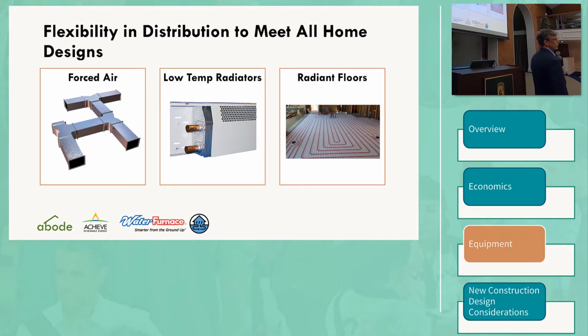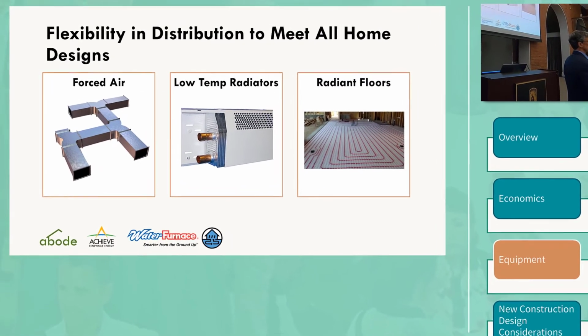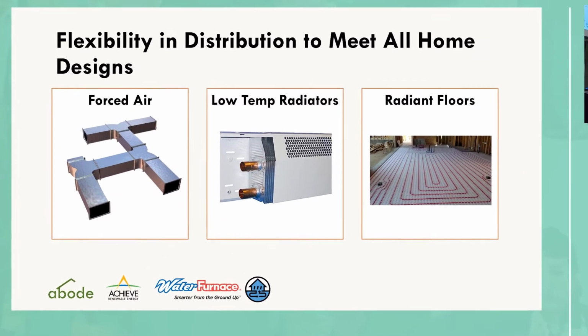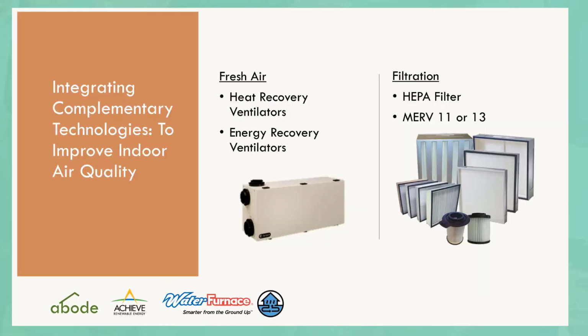can make things warm or cold. And without ducting, you don't get the air conditioning, unless you do something fancy like a chilled beam, but you're not going to do that in a house. Pairing with radiant floors is exceptionally efficient because the fluid temperatures are lower, so the COP on the water-to-water geothermal units can be very high because there's less of a temperature differential they have to account for.